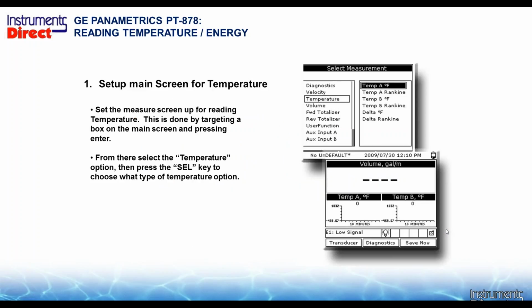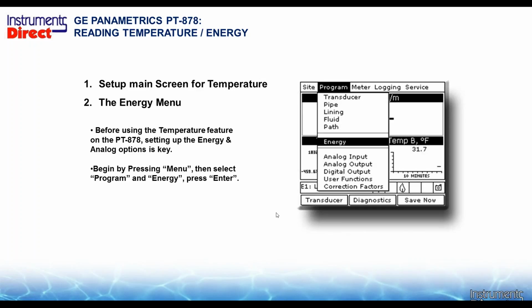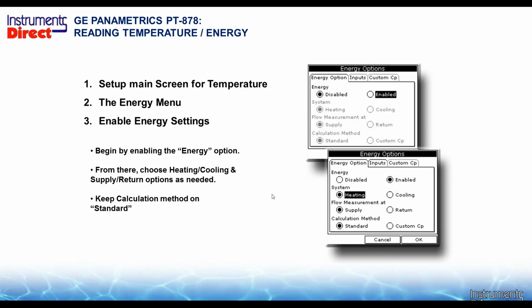So to set up the temperature, we need to go in and set up the screen for temperature. We select the measurement screen for reading temperature by targeting the main screen and pressing enter. From there we select, guess what, temperature, and from the options we press the select key to choose the type of temperature option. Before we use the temperature feature in the PT878, we need to set up the energy analog inputs. So here we go: we press menu, select program and energy, and then press enter.